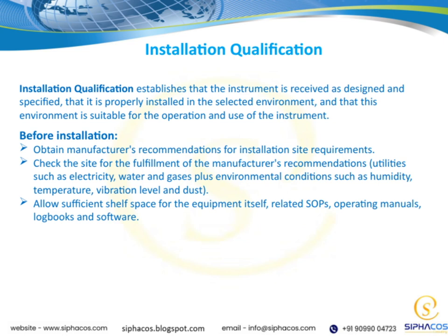Additionally, it's smart to allow enough shelf space. This space isn't just for the equipment itself, but also for related SOPs, operating manuals, logbooks, and any software you might need. All these steps help set the stage for a successful installation. Remember, a proper installation isn't just about the equipment, but also about creating the right environment for reliable, consistent operation. That's the essence of installation qualification.